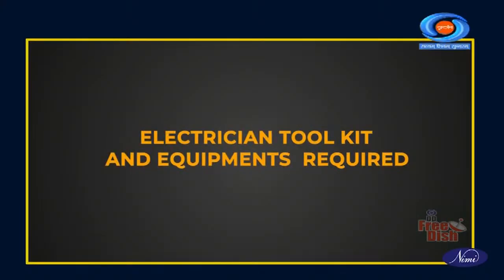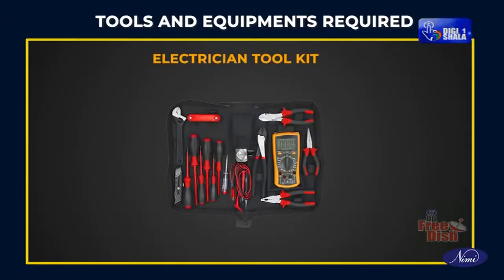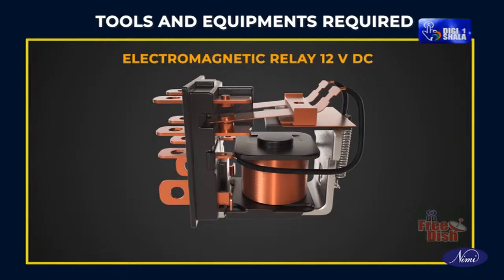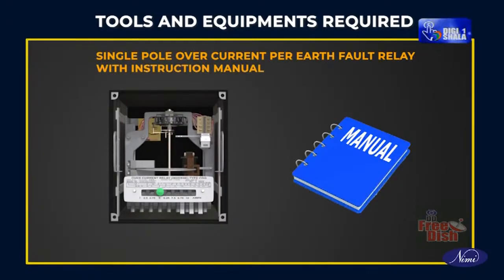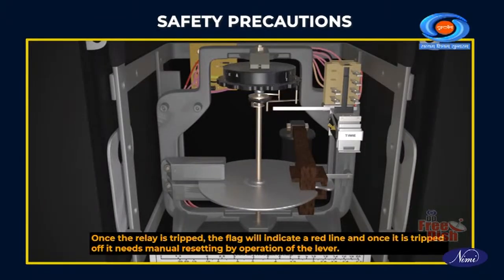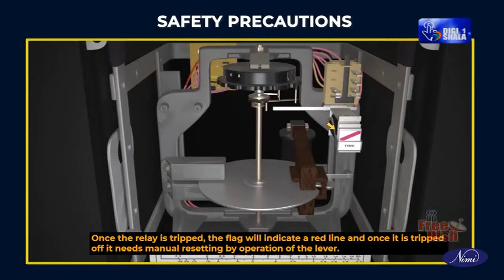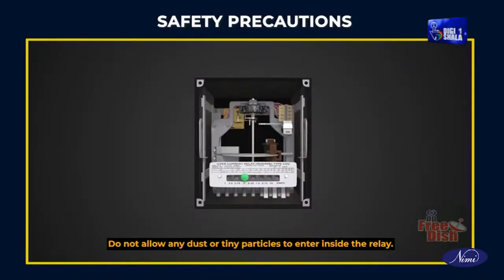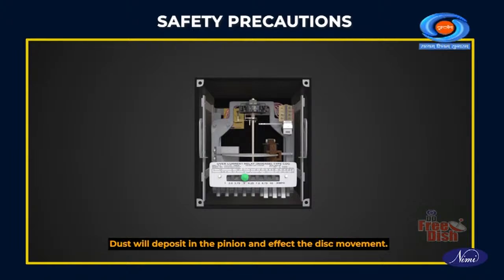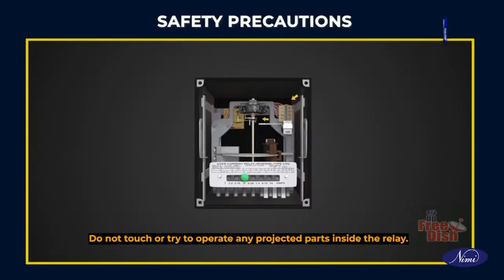Electrician toolkit and equipment required: electrician toolkit, multimeter, electromagnetic relay, 12 volts DC, single pole overcurrent and earth fault relay with instruction manual. Safety precautions. Once the relay has tripped, the flag will indicate a red line, and once it has tripped, it needs manual resetting by operation of the lever. Do not allow any dust or tiny particles to enter inside the relay. Dust will deposit in the pinion and affect the disc movement. Do not touch or try to operate any projected parts inside the relay.